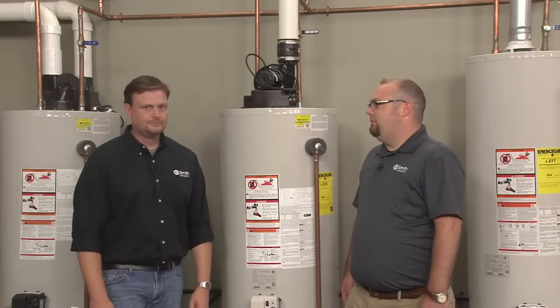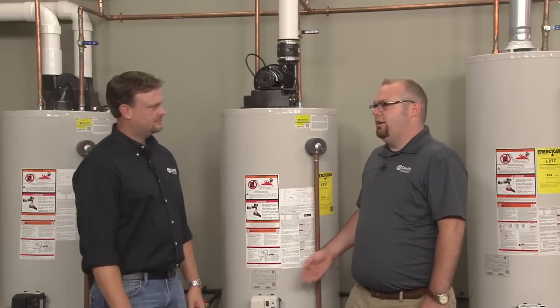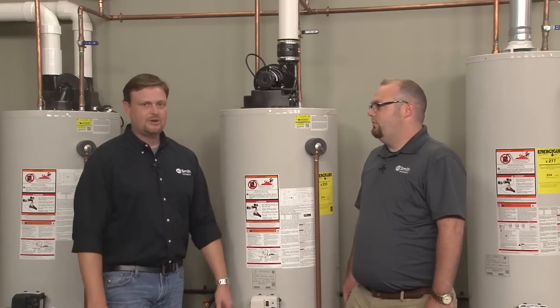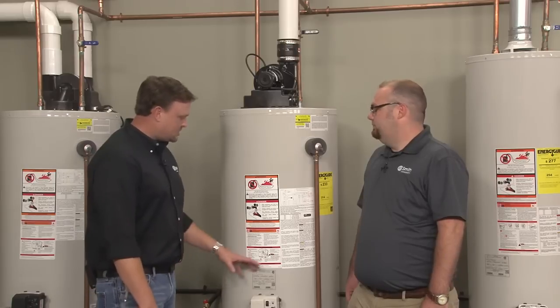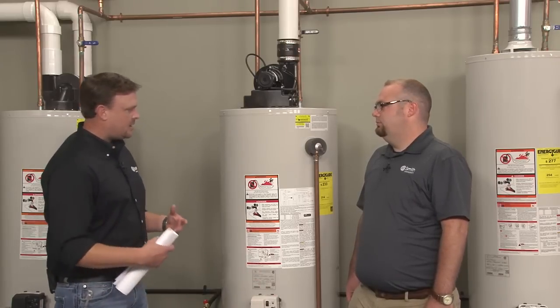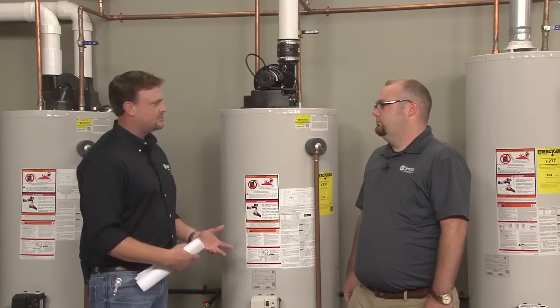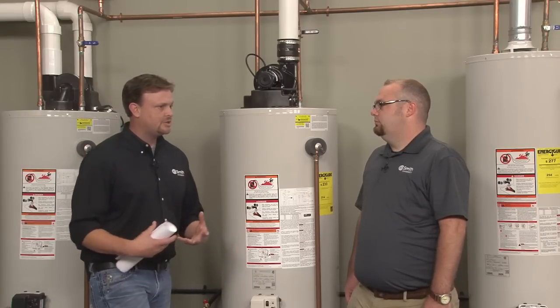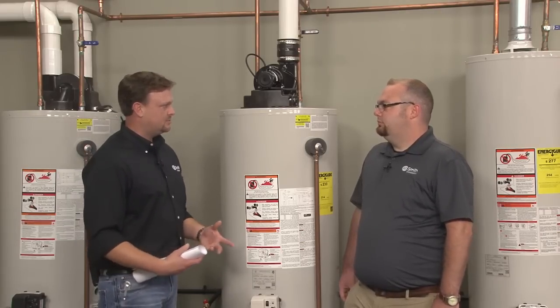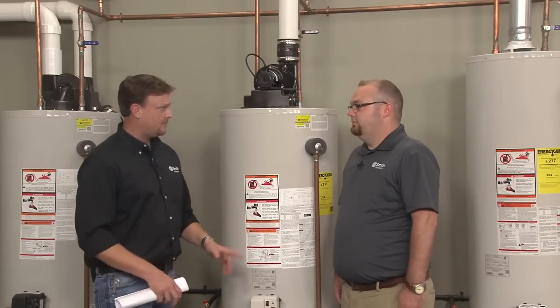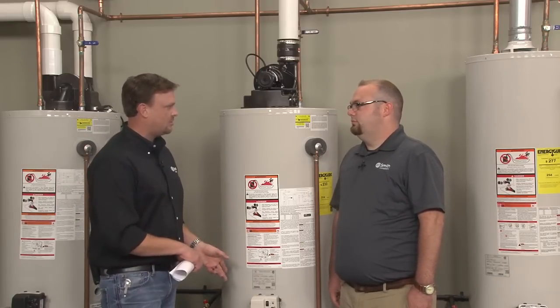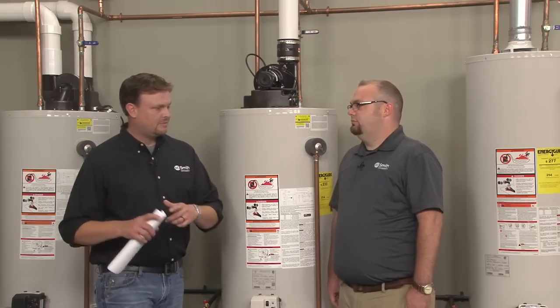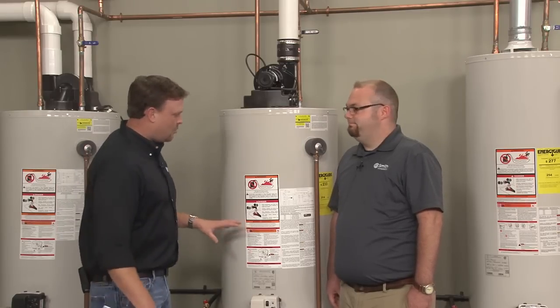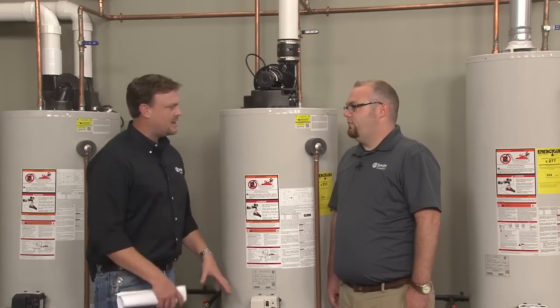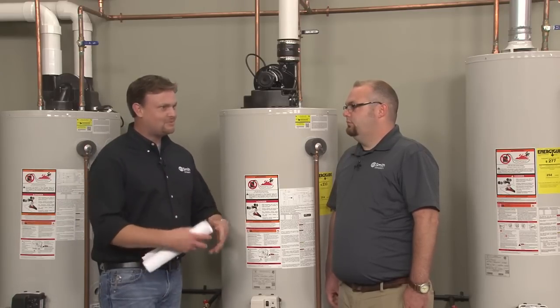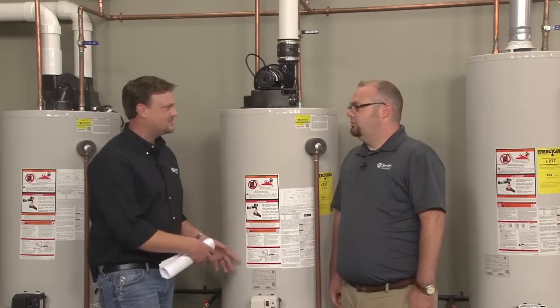Yeah, they're pretty much the same from here on out. The only thing that's a little bit different is what it does for the blower. Yeah, we talked about that. All right, so one of the ones I want to talk about is a flammable vapor sensor lockout. That's something that usually has a reset procedure involved. Correct. There is something different about this water heater than the IntelliVent, but what does it really mean when that goes out? I know it means we sense flammable vapors, but really, what does that mean?